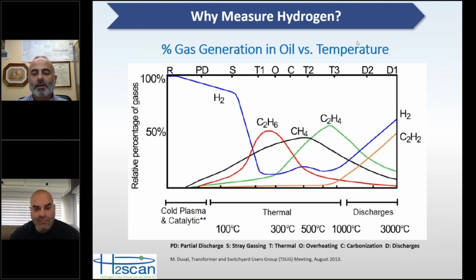And as those start dropping off, as you get up to around 700 to 1,000 degrees C, you primarily get acetylene and lots of hydrogen. And so with this graph, you have to keep in mind that this is on a percentage basis. So during that mid-range, your hydrogen value isn't actually going down. The hydrogen value is continuing to increase, but that's on a percentage basis. You're generating the other gases in higher concentrations than you are hydrogen.